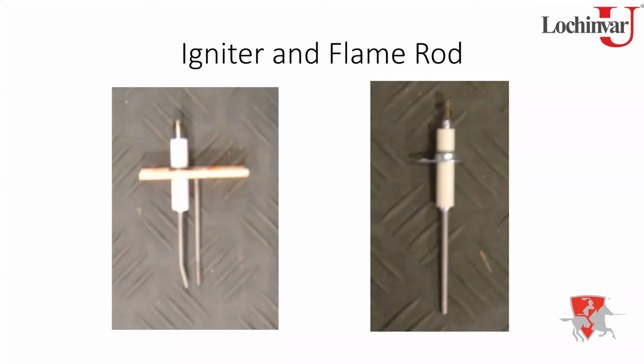You need at least a minimum of 1 microamp to prove the burner flame in. So if you've got anything less than 1 microamp, basically you're going to flame out. And you get 4 tries for ignition because they're under 400,000 BTUs. Right? You get 4 tries for ignition before you will go into what's called a lockout or a flame fail condition.